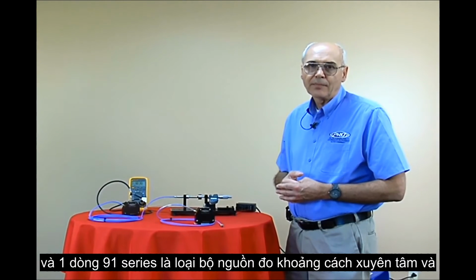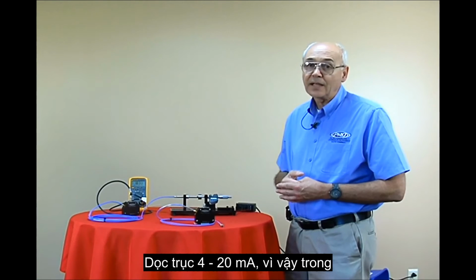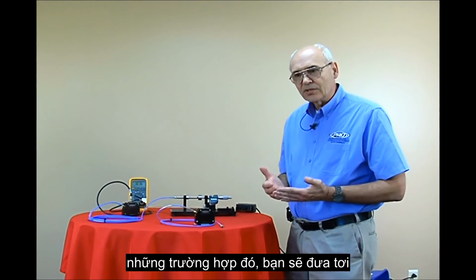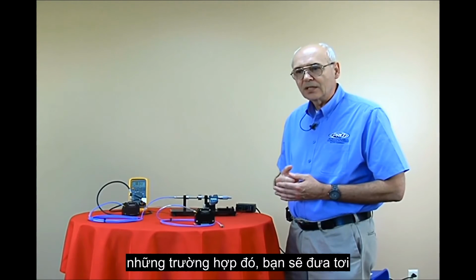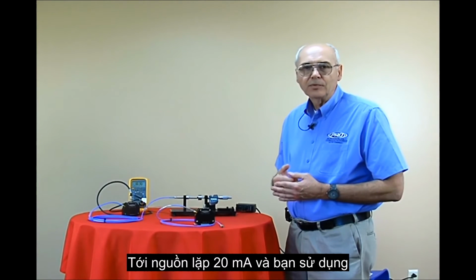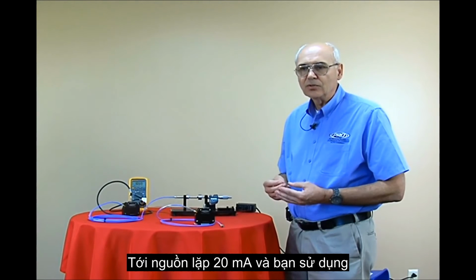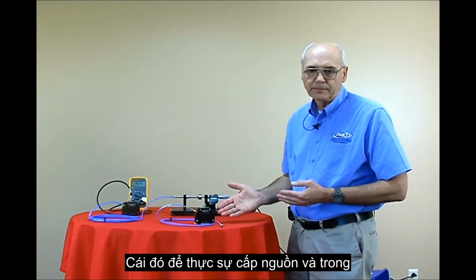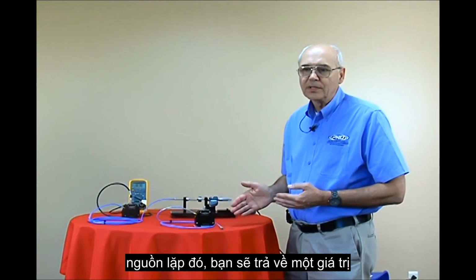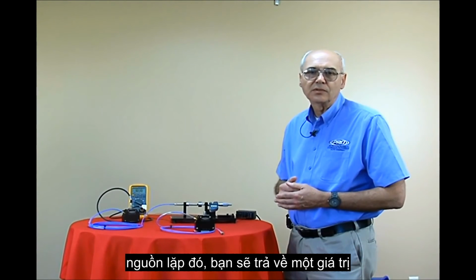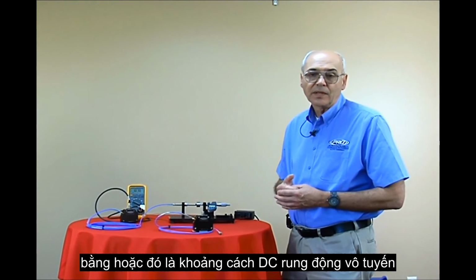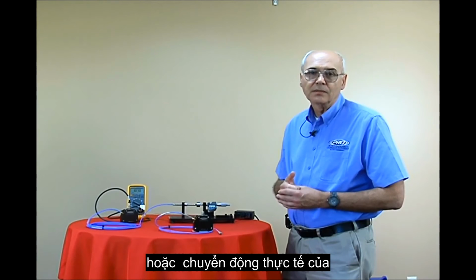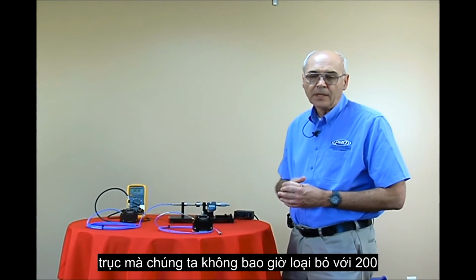These are gap, radial, and axial 4 to 20 milliamp drivers. In those instances, you would take the 4 to 20 milliamp loop power and use that to actually power the driver. In that loop, you would return a value equal to either the DC gap, the radial vibration, or the actual movement of the shaft.